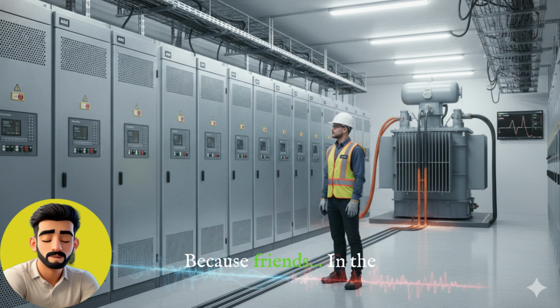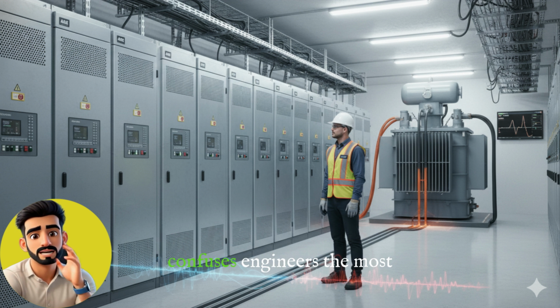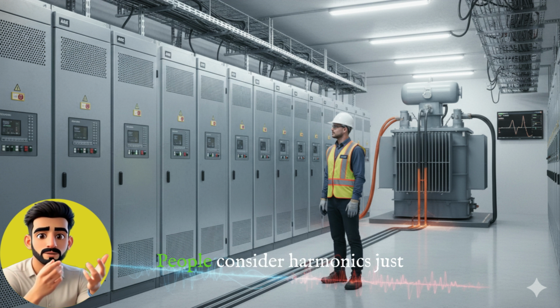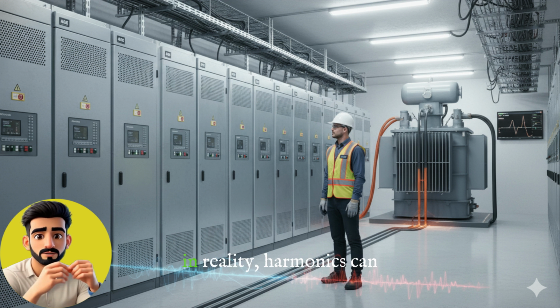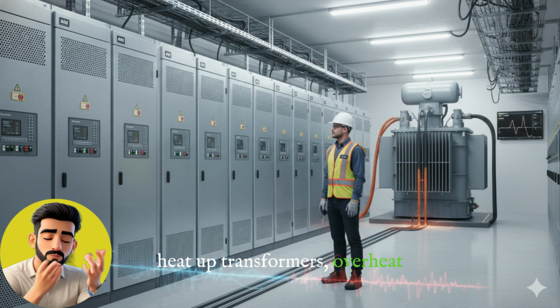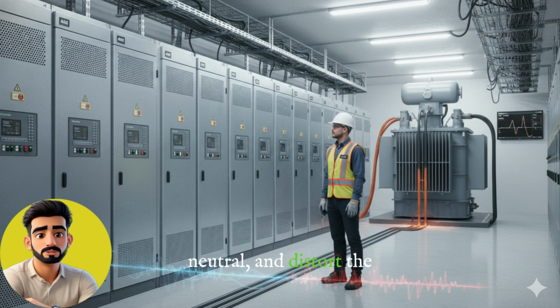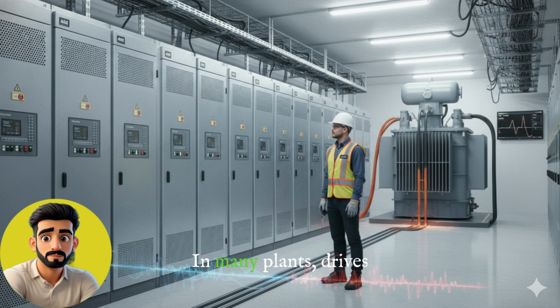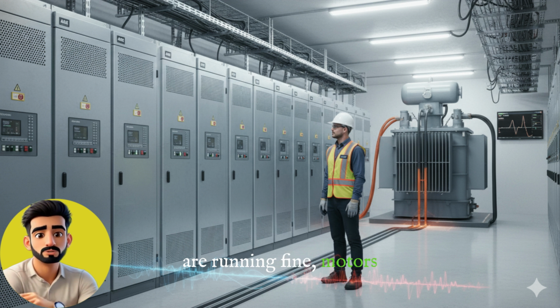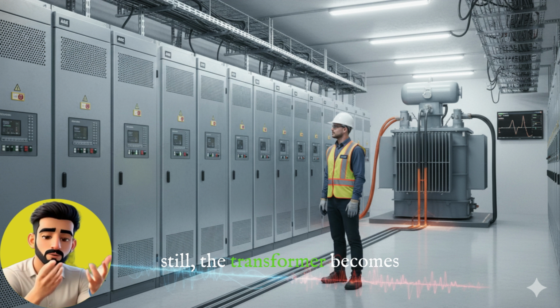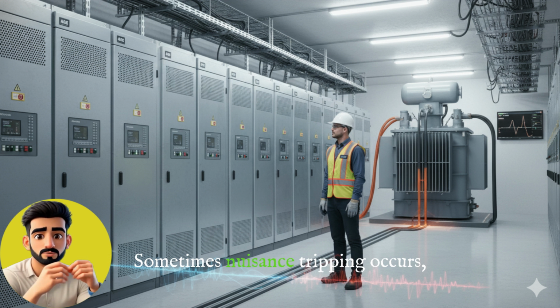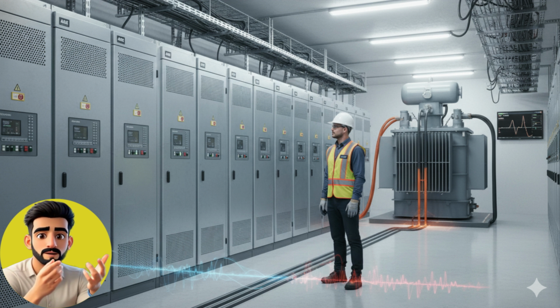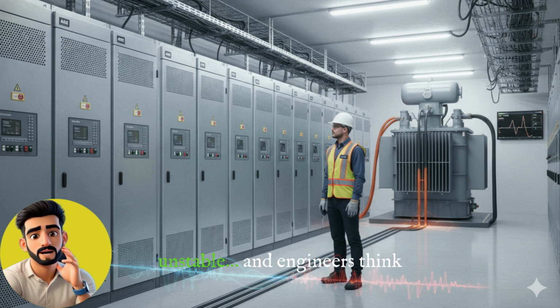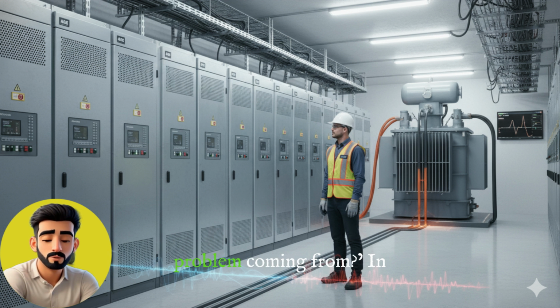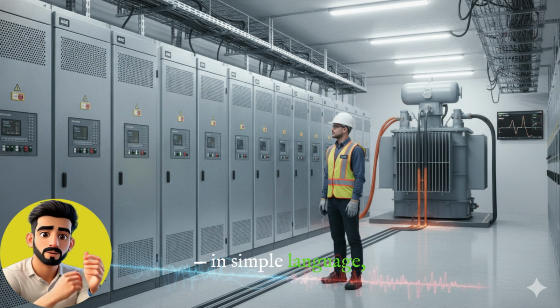Because, friends, in the world of VSD, there's one thing that confuses engineers the most: harmonics. People consider harmonics just a theoretical topic, but in reality, harmonics can heat up transformers, overheat cables, generate current in neutral, and distort the voltage of the entire system. In many plants, drives are running fine, motors are working properly, but still, the transformer becomes unusually hot. Sometimes nuisance tripping occurs, sometimes breakers warm up, sometimes the generator becomes unstable, and engineers think, where is this problem coming from?